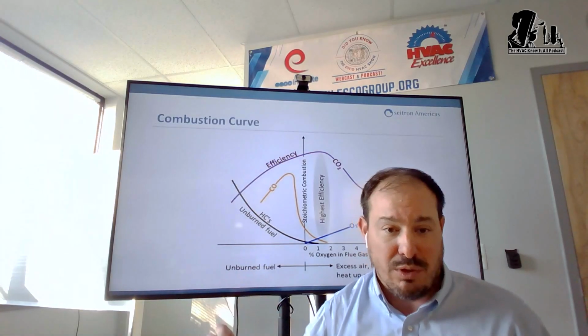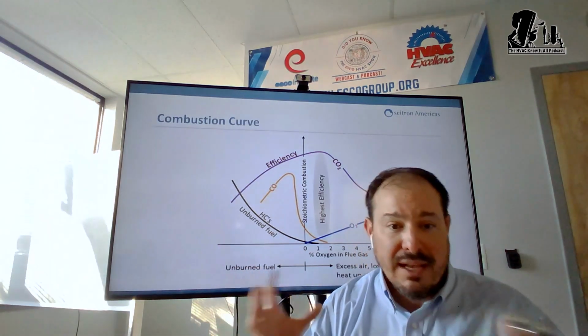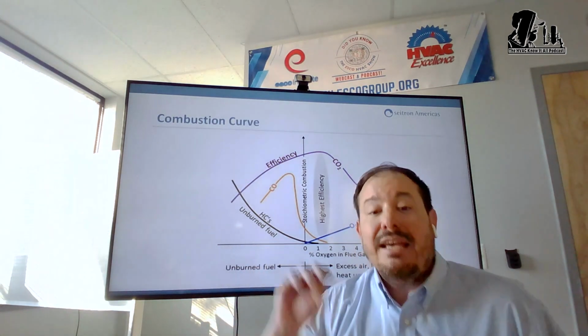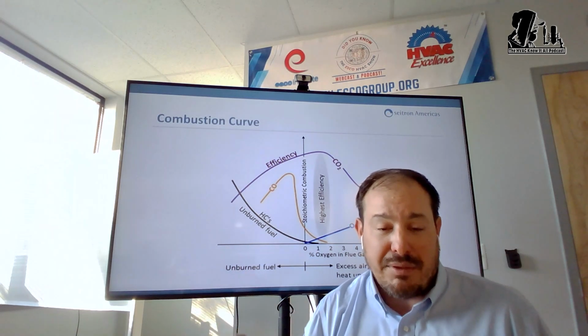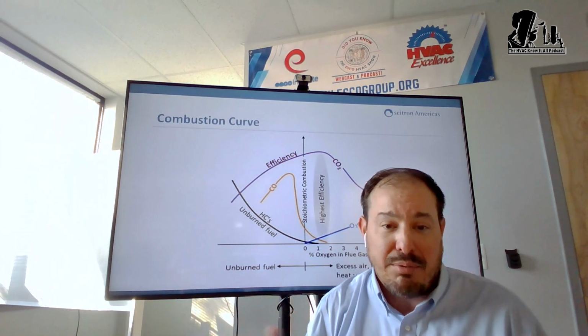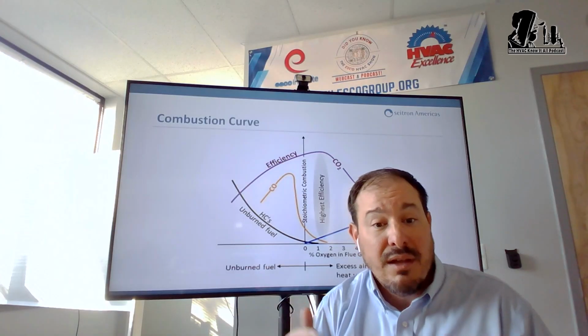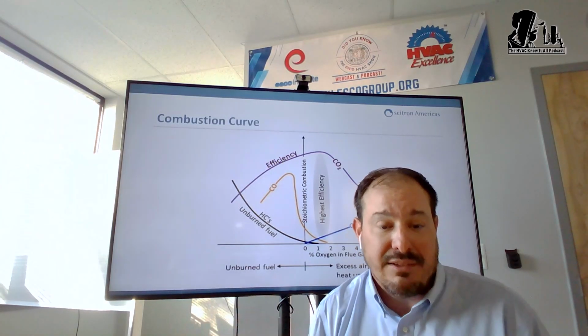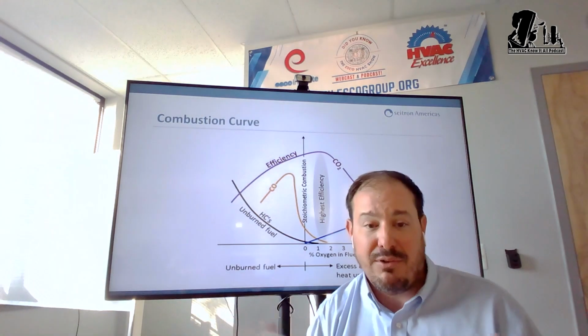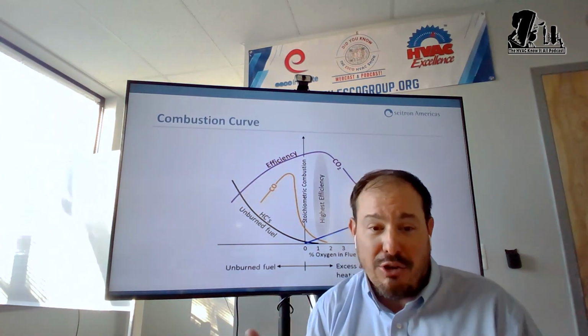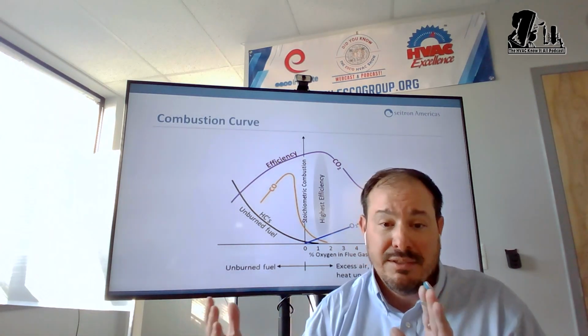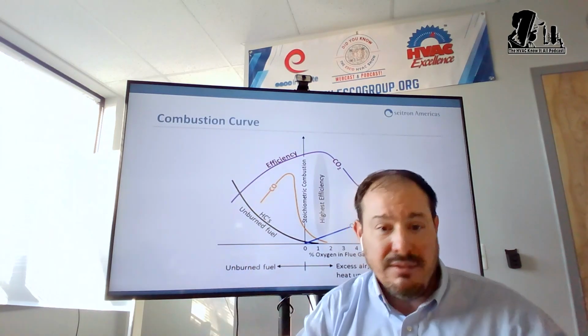I jokingly always say there are 2 E's in combustion: efficiency and emissions. A lot of us in the HVAC world live in the efficiency world, meaning we look at oxygen, CO, CO2, how efficient and how safe it's running. Then there's the emission side, and those guys typically care less about how efficient a boiler is running, but more about what the emissions look like, since they need to create an emissions report. So when guys ask me for NOx analyzers, I immediately know they live in the emissions world, but both are happening, right? It doesn't matter what you're burning, whether it's a boiler, your automobile, or an engine, it's all mixed with air and fuel.